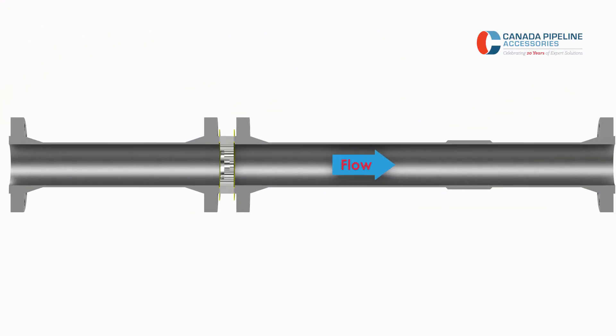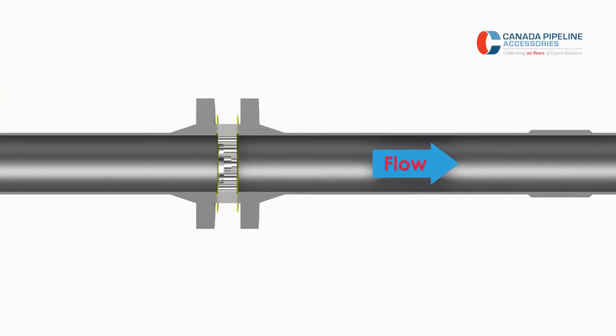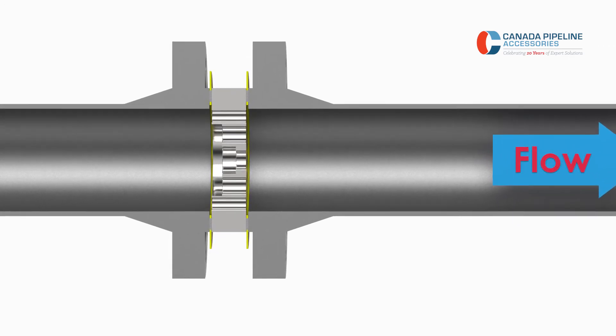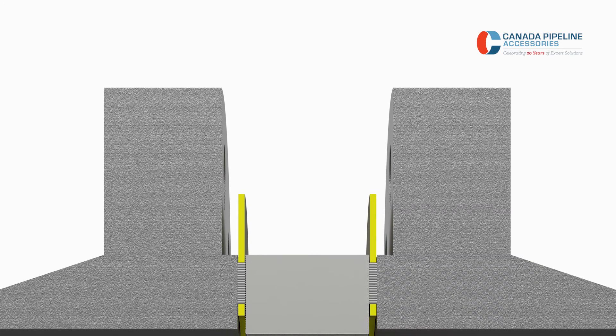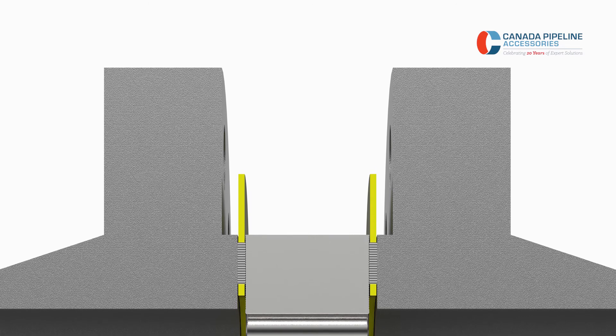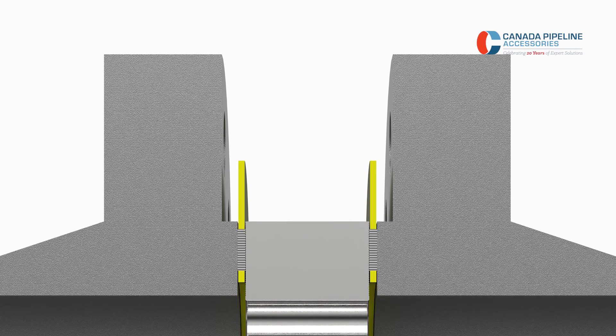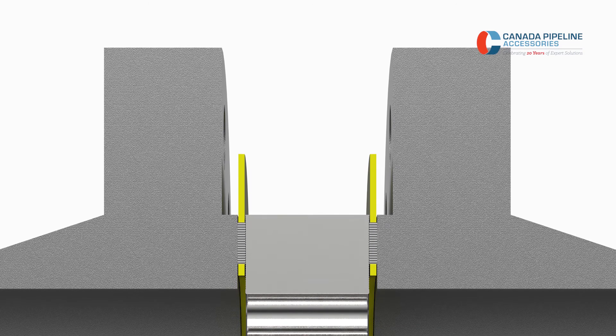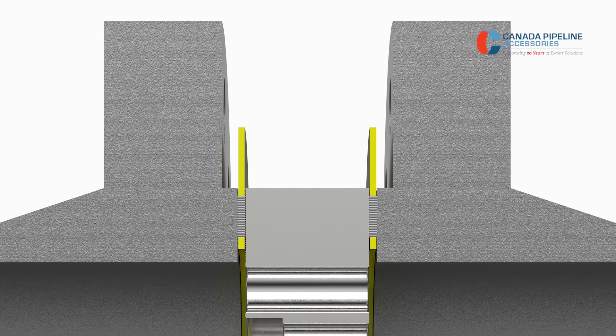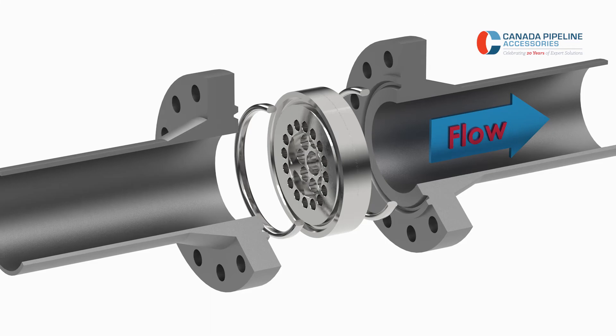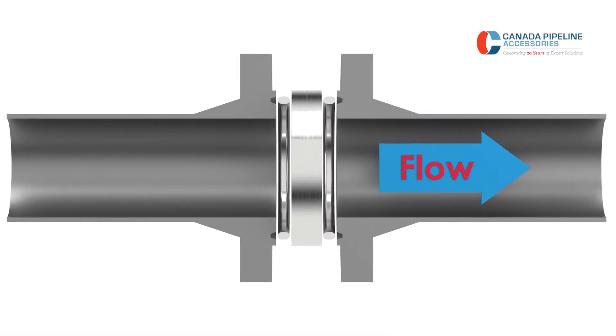CPA type B flow conditioners cannot be centered within the pipe as they are simply sitting between the flanges. Extra care must be taken to ensure that the flow conditioner is centered against the raised face surface, as any misalignment can result in measurement errors or outright blockage of the outer flow conditioner holes. CPA type D flow conditioners will be automatically centered due to the RTJ gaskets when the flange is tightened.